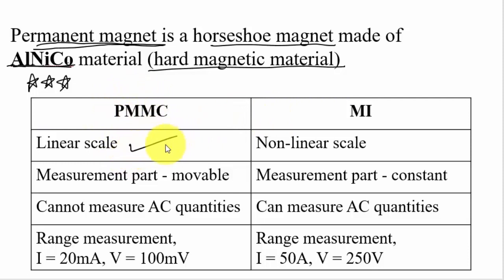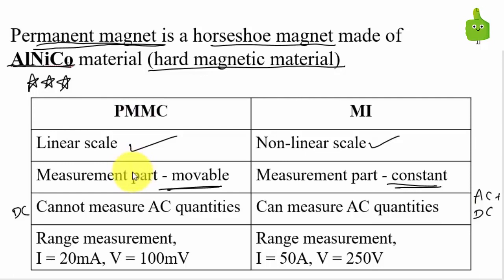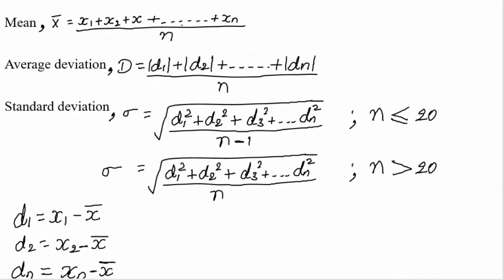Comparing PMMC and moving iron: PMMC uses a linear scale; moving iron uses a non-linear scale. The moving part in PMMC is movable; in MI it is fixed. PMMC can measure only DC quantities; moving iron can measure both AC and DC. Range is restricted in PMMC — maximum current up to 20 mA and voltage up to 100 mV. Moving iron can measure current up to 50 A and voltage up to 250 V, so moving iron is preferred for most applications.